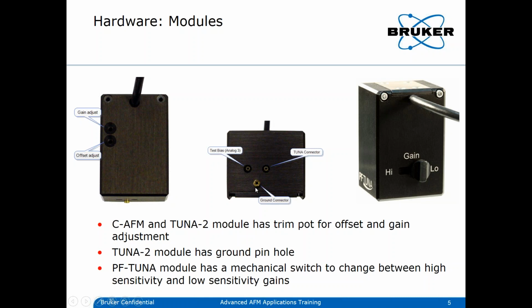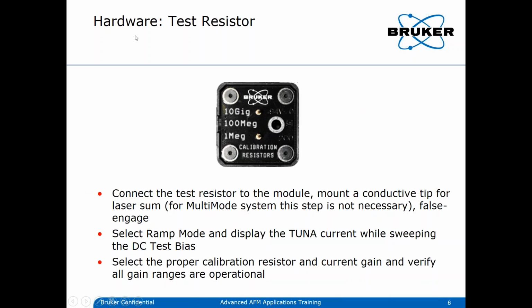And the TUNA 2 module, in addition, has also a ground pinhole where you basically make contact, in the case of measuring in TUNA mode, to reduce the noise of the system. With all the possible sets or modules comes also a test resistor, which has a range from about 10 gigaohm to 1 megaohm.